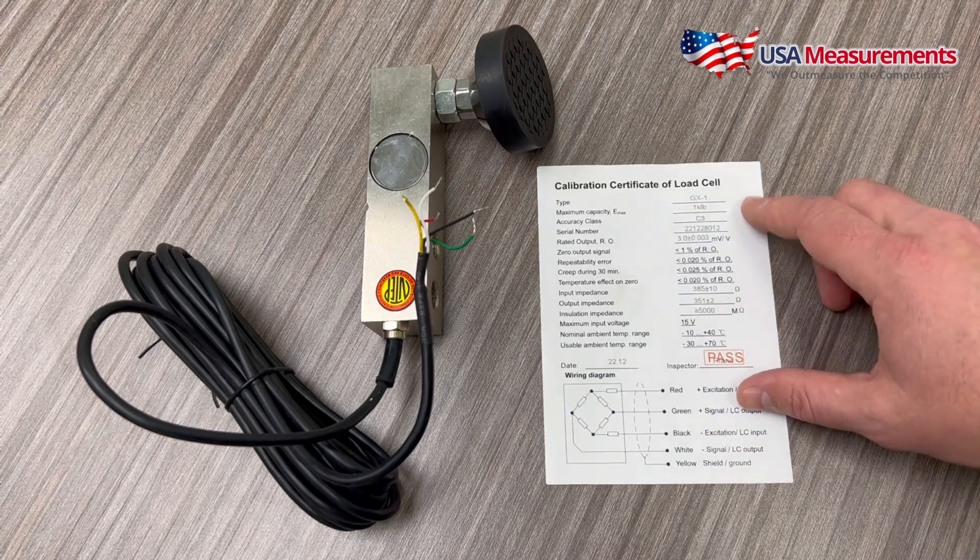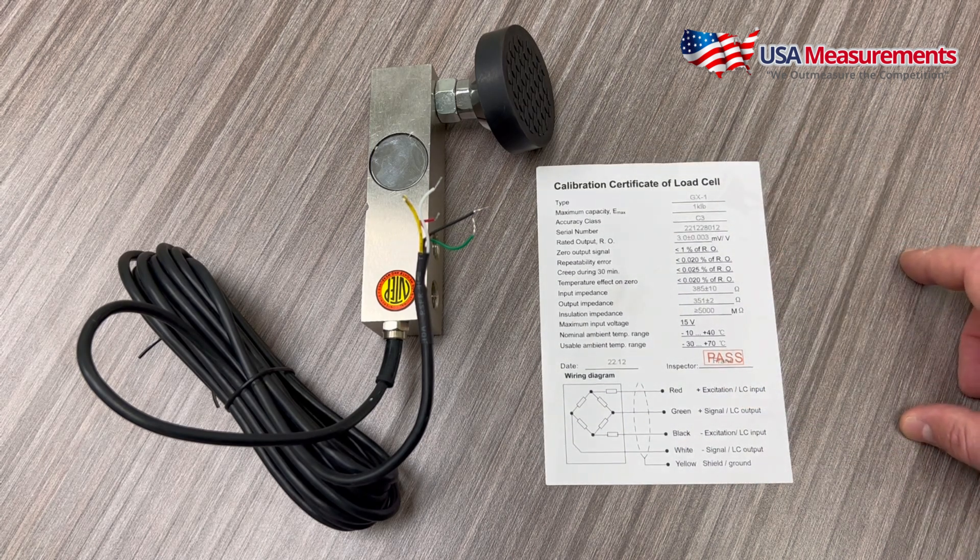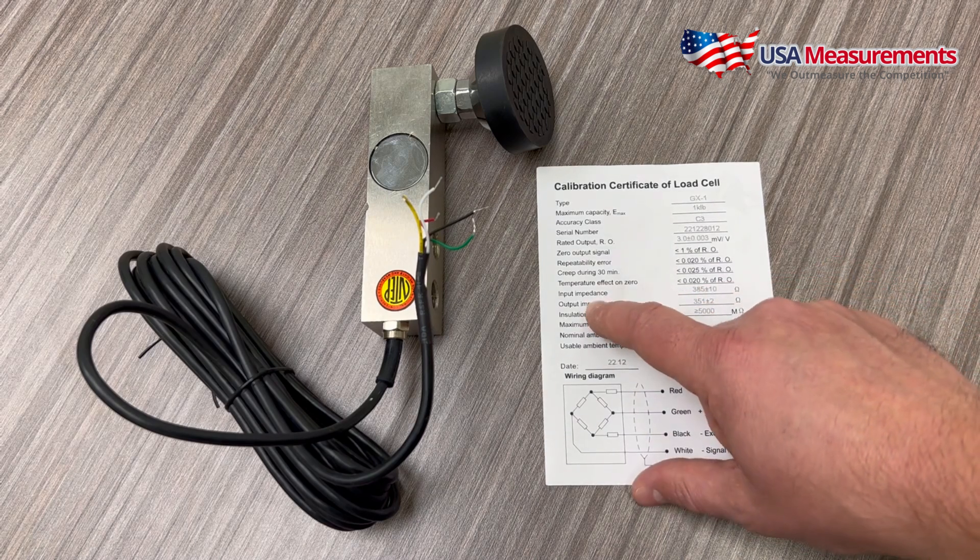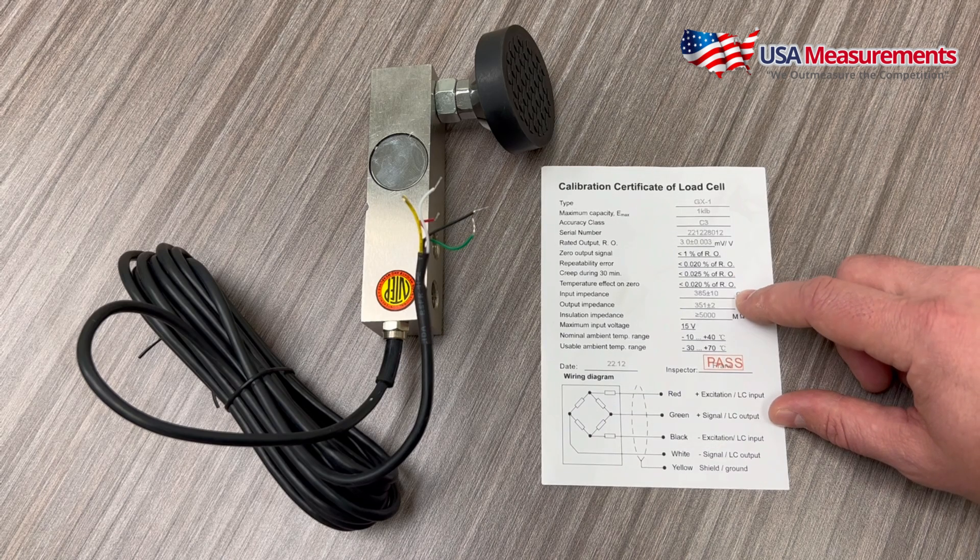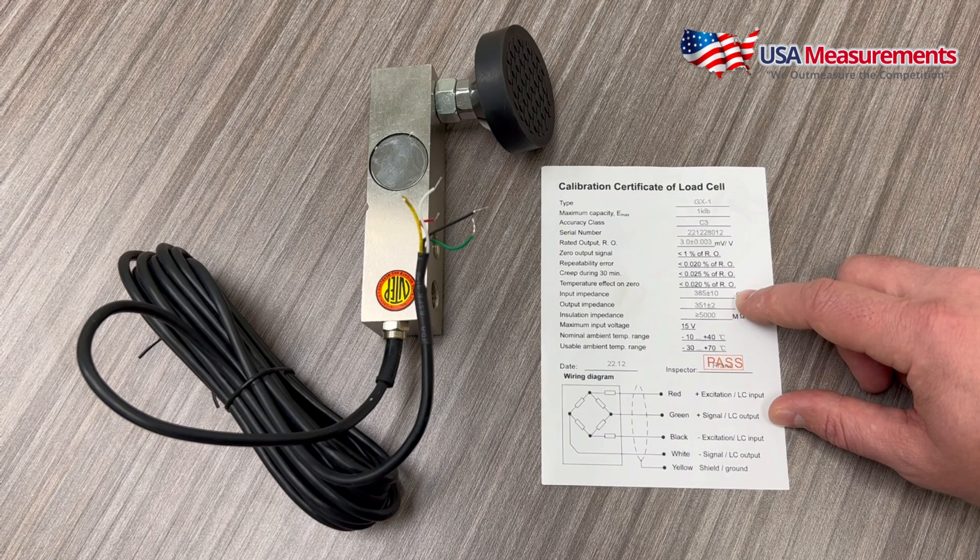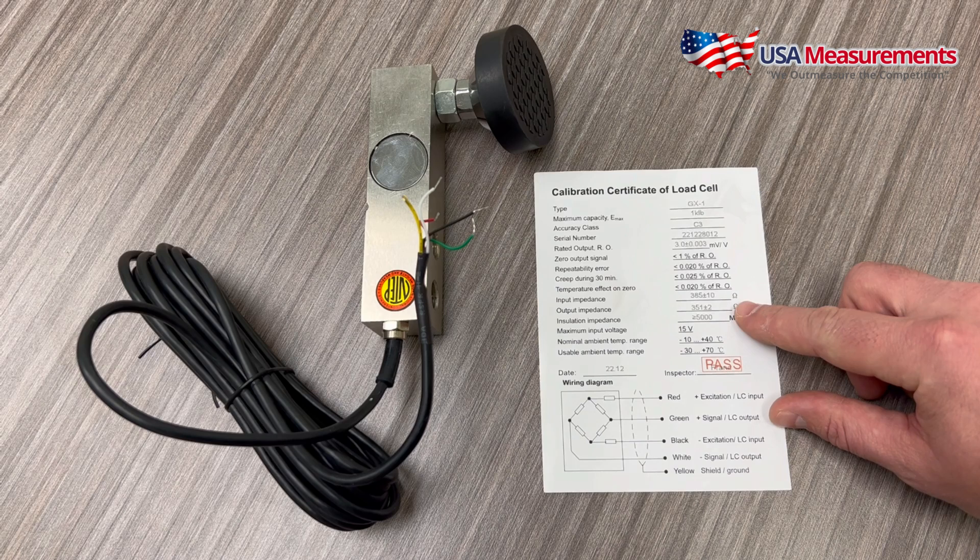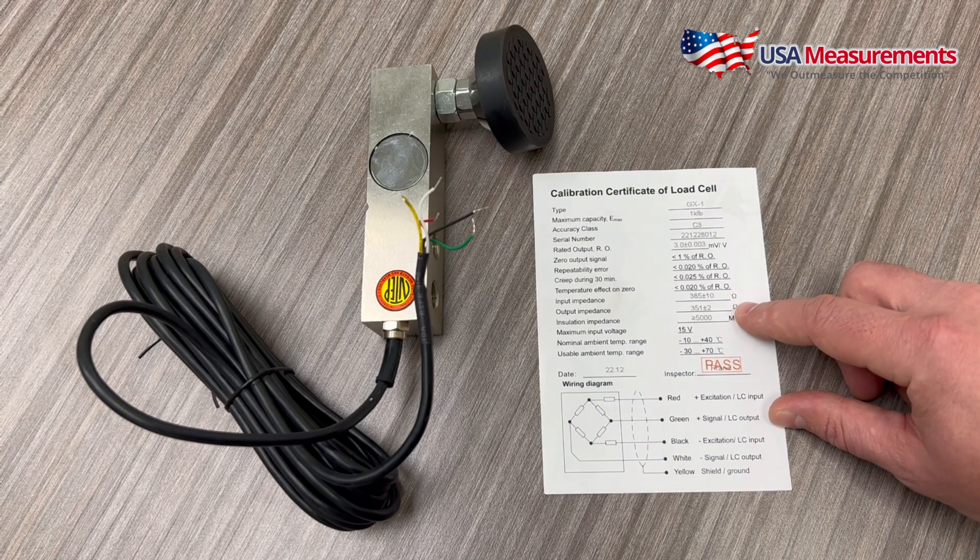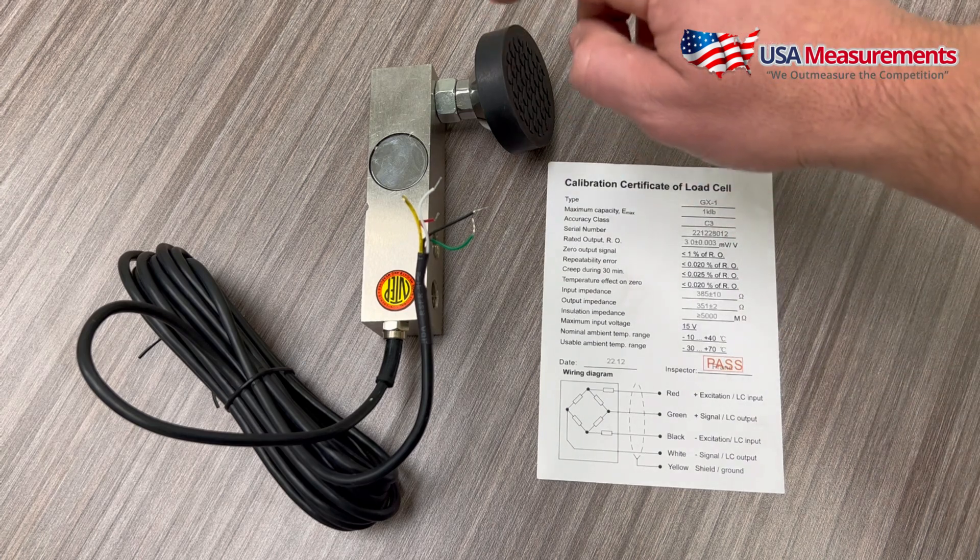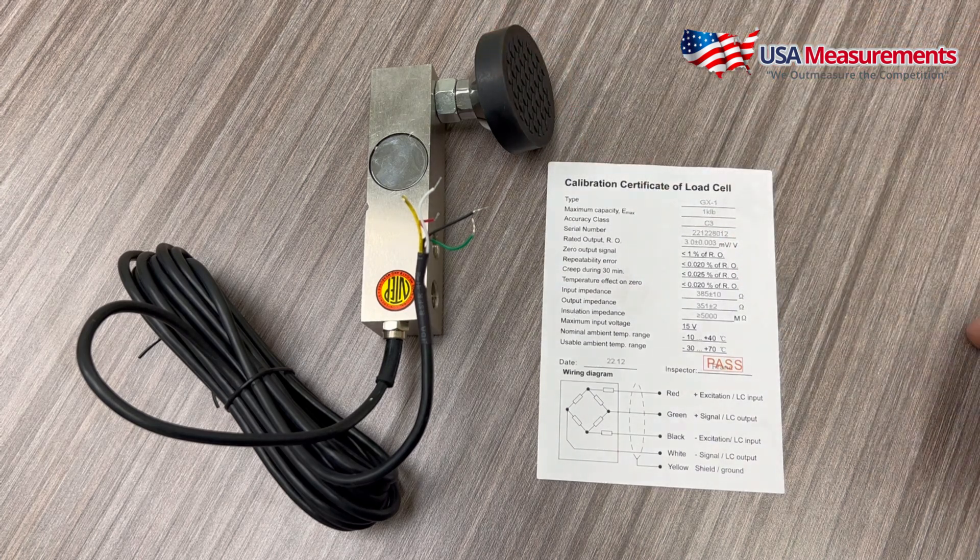Now first, if you have a calibration certificate, this will be helpful to tell us what the input impedance and output impedances of the load cell are. So the input impedance is 385 with plus or minus 10 ohms, and the output impedance is 351 with plus or minus 2 ohms.